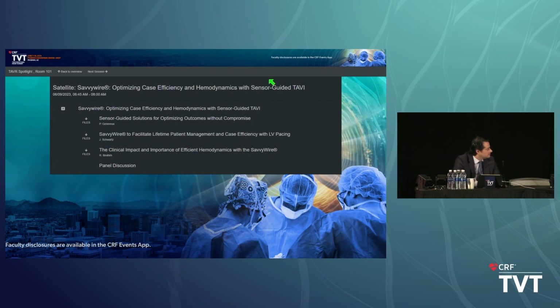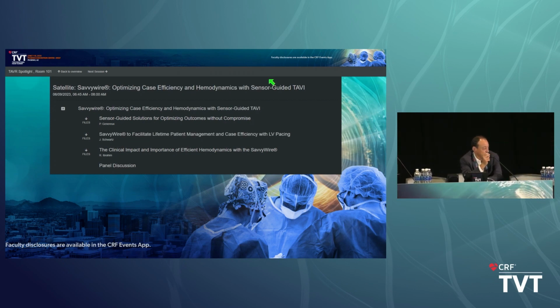There's a specific zone to put your alligator clamp on the wire, but you can pace anywhere on this wire with the clamp. So if you want to remove, let's say it's an Edwards valve, and you want to remove your delivery system, you can put your alligator clamp at the end of the wire, and it's still pacing, even if it's not in the zone that's covered by the insulation. You remove your delivery catheter safely, and then you can just switch the clamp. And if you're not pacing, it's just for a few seconds. I see. Thank you. That's what we do.